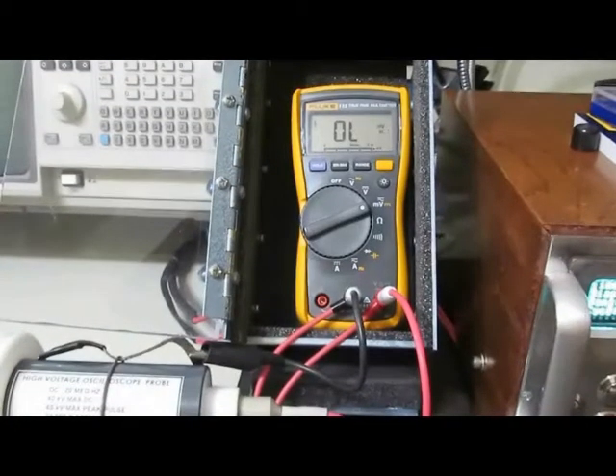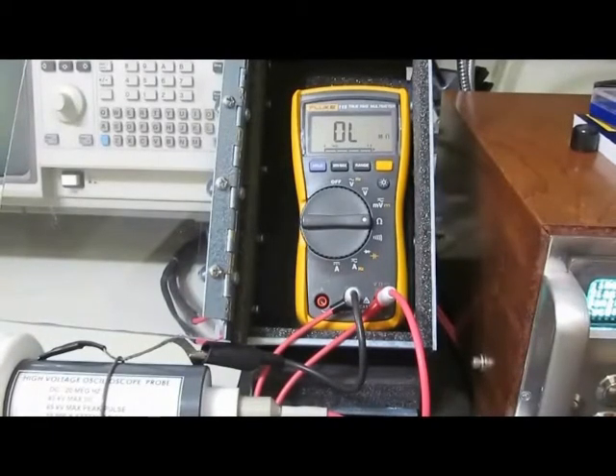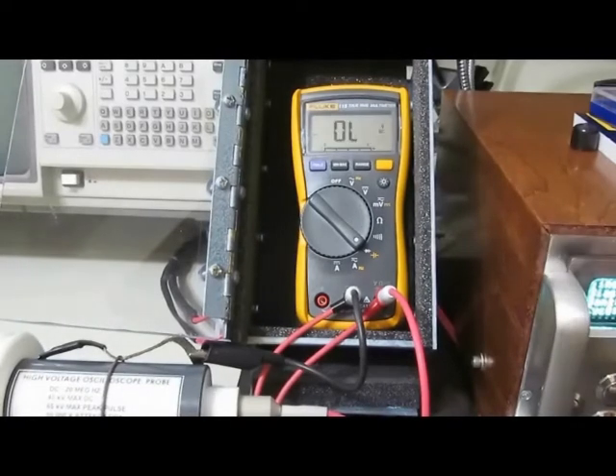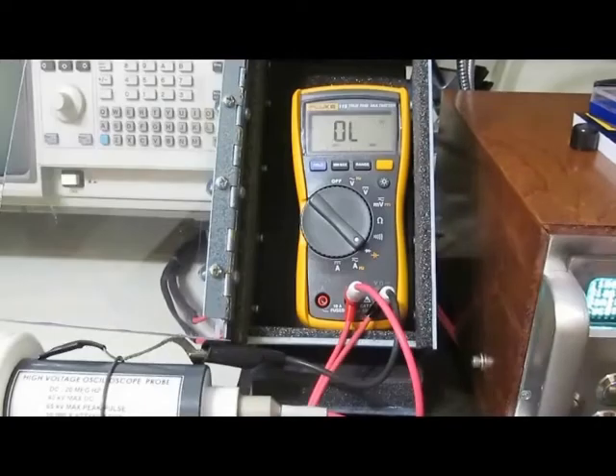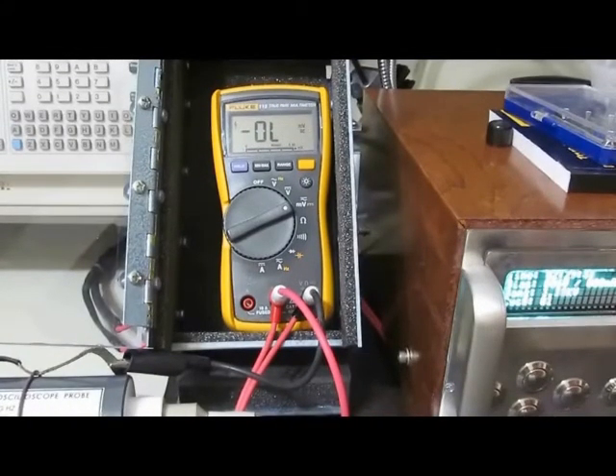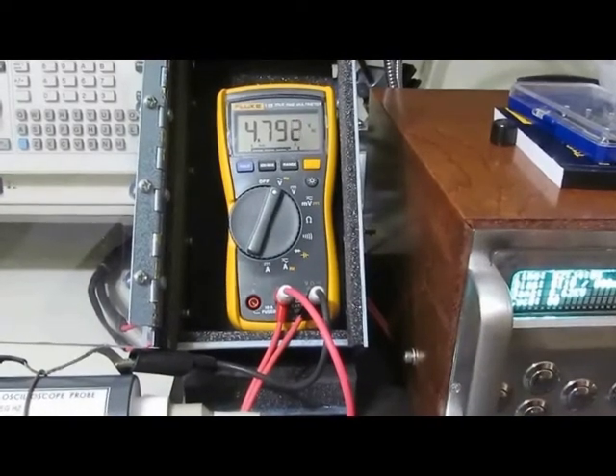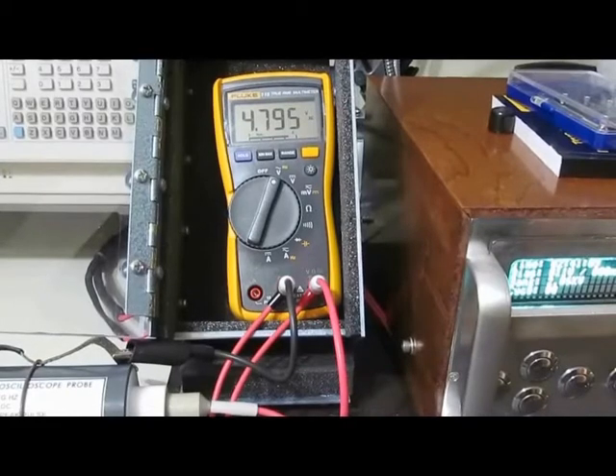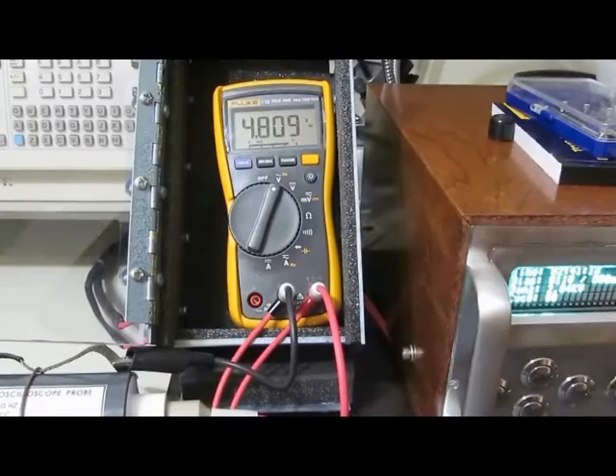This will be 5,000 volts. Alright, that's the end of the test. We'll go ahead and functional test. Okay, it survived 5 kV.